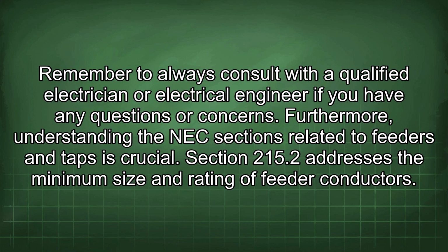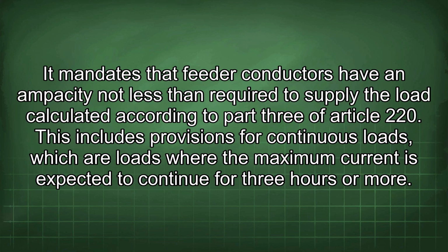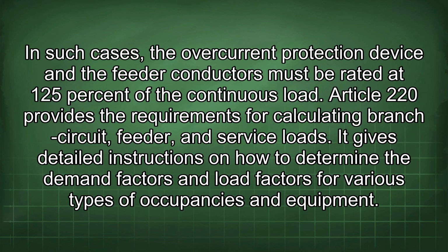Furthermore, understanding the NEC sections related to feeders and taps is crucial. Section 215.2 addresses the minimum size and rating of feeder conductors. It mandates that feeder conductors have an ampacity not less than required to supply the load calculated according to Part 3 of Article 220. This includes provisions for continuous loads, which are loads where the maximum current is expected to continue for 3 hours or more. In such cases, the overcurrent protection device and the feeder conductors must be rated at 125% of the continuous load.